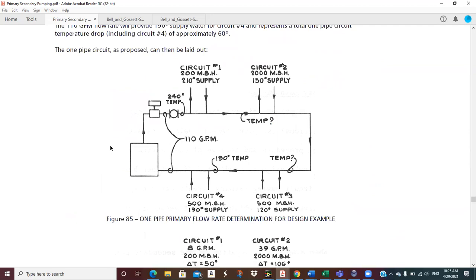They can make it work for an example here that has 4 secondaries, but if you have a big building with lots of secondaries, I just don't think this is going to work for you. Because what happens is we're starting off with 240-degree water. Then he pulls whatever the capacity of this coil is, 200,000 BTUs an hour, and the temperature drops because he pulls water out and dumps it right back into the primary supply. There's only one pipe.